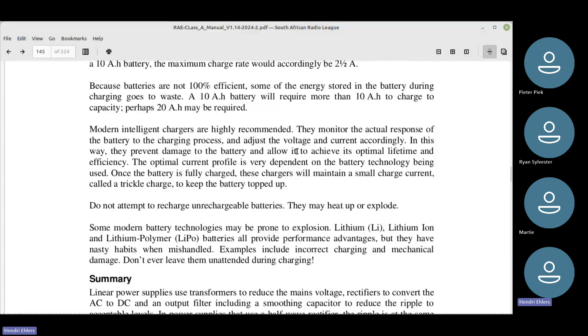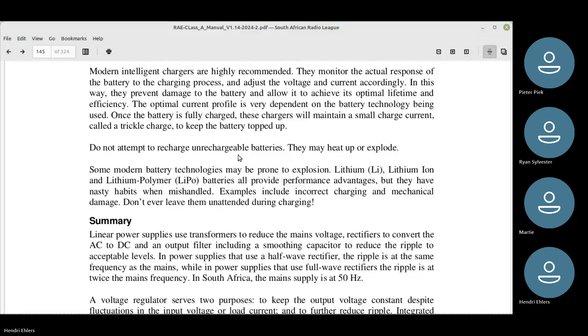But they are dangerous. Cycle count is also quite high on lithium compared to all the other chemistries. Yeah, they last long, but they are very flammable and very particular about how they are charged. They've got what they call a battery management system, BMS, inside. Most lithium batteries have a BMS. If it doesn't have a BMS, you'll have to use a very intelligent charger. I've got model helicopters, and your charger actually monitors each cell individually, so that you don't overcharge any one of them. If you do, they swell up, and when the air, oxygen, and lithium meet, you've got a fire.